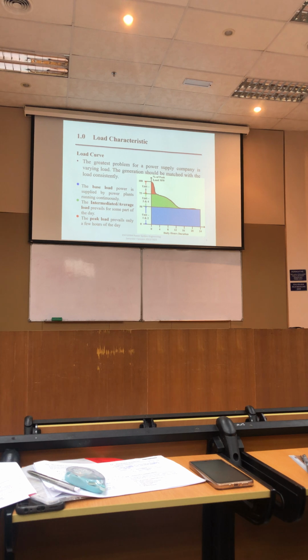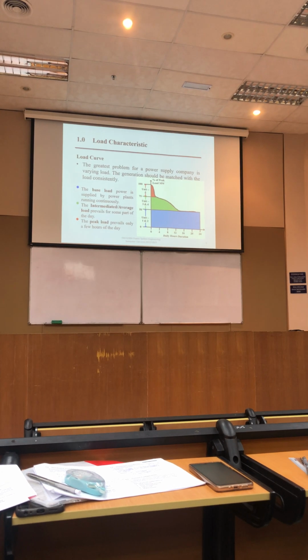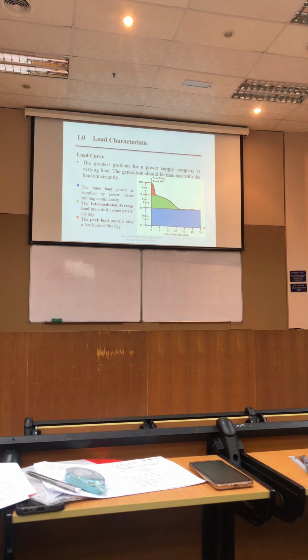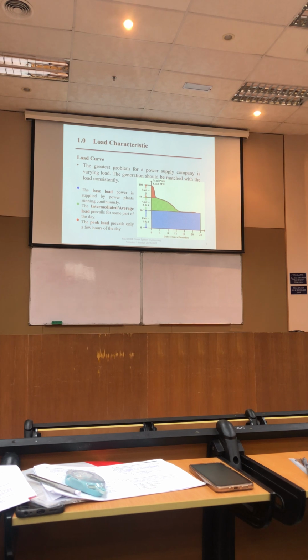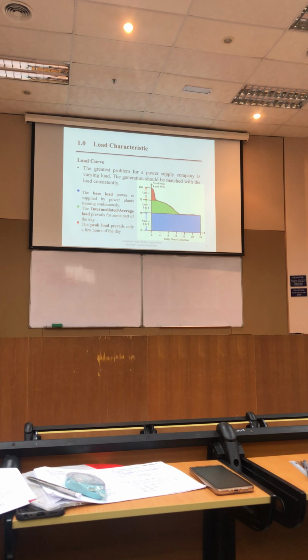Okay. For example, your power station can supply up to 150 megawatts. Okay, is it possible for a power station to have only one generator that can provide 150 megawatts? Why you don't want to? Normally, engineers will not develop only one generator that can provide the whole power output, the whole capacity. Why? Yes, why? The generator is fine. Okay, if the generator is under maintenance, maybe it's broken or at fault, so we have to do maintenance. So what will happen to 100 megawatts load that is connected to the power station? Definitely, all of them will black out.